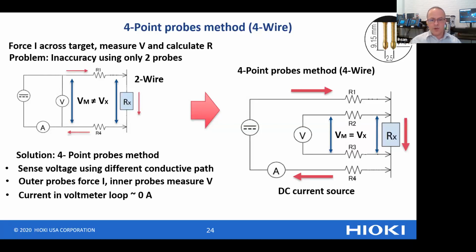And so within the voltmeter loop, the current is essentially zero because voltmeters have a very, very high input impedance. So as such, when the current is essentially zero, the drop that's measured by the voltmeter is essentially the same as the drop across the target. That way, we're able to essentially cancel out the IR drop due to R1 and R4. And R2 and R3, which is the resistance of the voltmeter leads, is essentially irrelevant because the voltmeter doesn't draw any current.